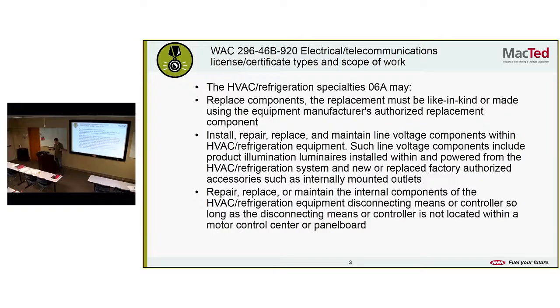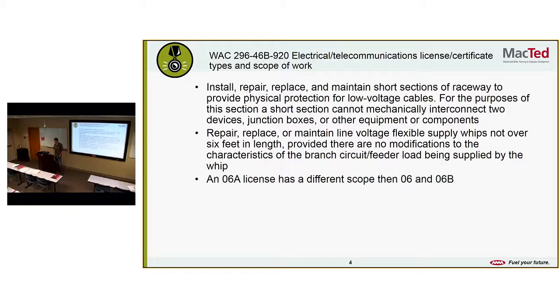You can replace any of the internal components as long as it's within the unit and it's not outside. So that's kind of what your 06A allows you to do. You can run short sections of conduit, but that's only for protection of low voltage. That's not like a line voltage circuit. That's just protection of low voltage. So that's within the 06A scope. And you can replace line voltage whips as long as they're 6 feet or under. So just so you guys know that.